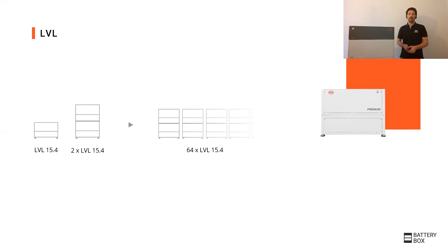2 LVL can also be stacked on top of each other, which leads to a significant reduction in the footprint required. Similar to the HVS and HVL, the correct configuration has to be verified in the minimum configuration list. Here, the required batteries for different use cases are listed, for example, for 1 or 3-phase systems, for on or off-grid, or for backup applications.